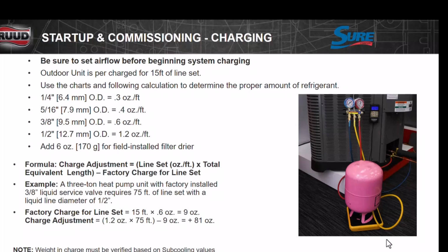So my sequence of installation would be, I would go and turn on the power outside, almost the first thing I do. That gets that compressor going with the heat, right? I would solder everything in. I would let the refrigerant flow through my lines while I'm doing my duct work. That way, we have that time to let that thing heat up and let the refrigerant go where it's going.